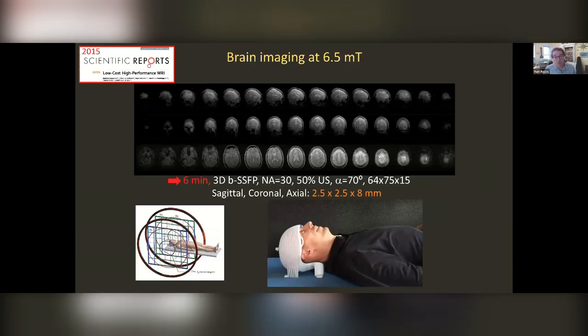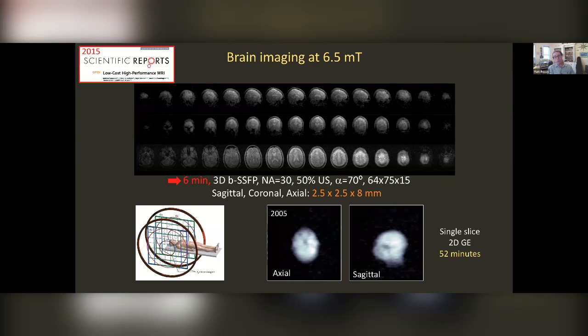fields as well. So when you do SSFP, and again, this is from our 2015 paper, this is 3D imaging that took about 6 minutes to acquire, about 2.5 millimeter in plane, 6.5 millitesla. Compare that to what I showed you earlier, which was in the same scanner at the same field strength with the wrong sequence, right? So if you want to do these things at low field, think about data rate, right?